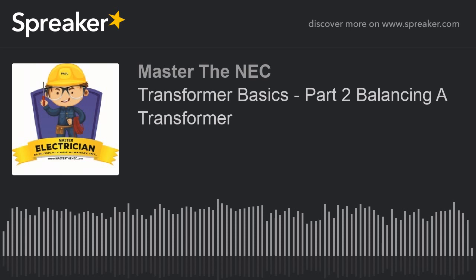I don't want to put the 4 on the 26 and then take that up to 30. And then I've got 30 on B and I've got 24 on A and C. I think I can balance it out a little better. So what I'm going to do is put 4 more on phase A. That third one, that last one. So then that's going to give me 28 on phase A. It really wouldn't matter if you put it on C or A. But I've got 28 on phase A, I've got 26 on phase B, and I've got 24 on phase C. That is about as balanced as I can get it. Okay? Across the board. All right?